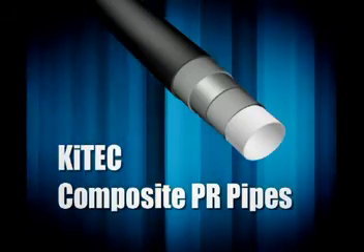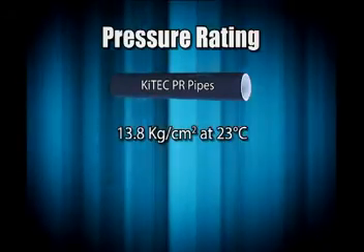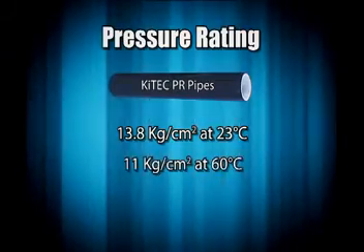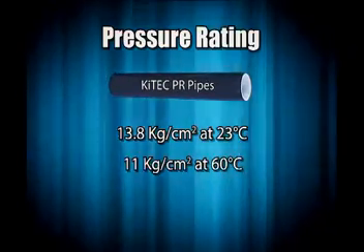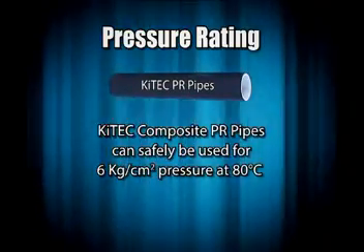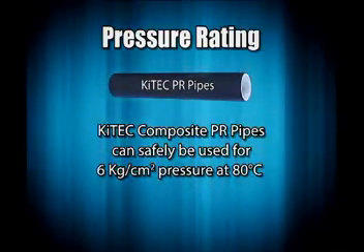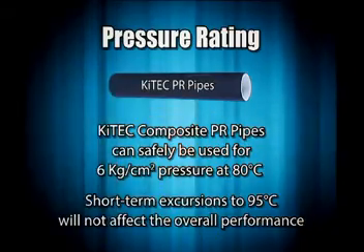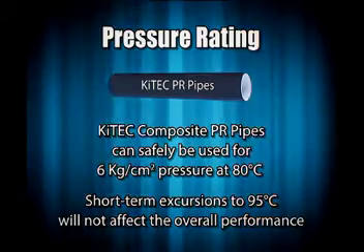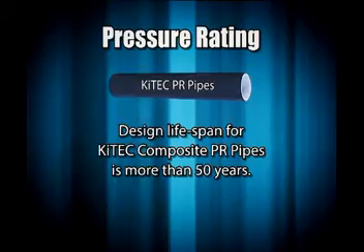KiTEC composite PR pipes. KiTEC composite PR pipes have a pressure rating of 13.8 kg per centimeter square at 23 degrees Celsius and 11 kg per centimeter square at 60 degrees Celsius. KiTEC composite PR pipes can safely be used for 6 kg per centimeter square pressure at 80 degrees Celsius operating temperature. Short-term excursions to 95 degrees Celsius will not affect the overall performance. Design lifespan for KiTEC composite PR pipes is more than 50 years.